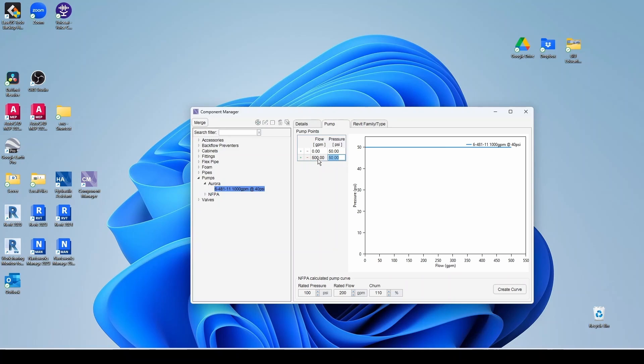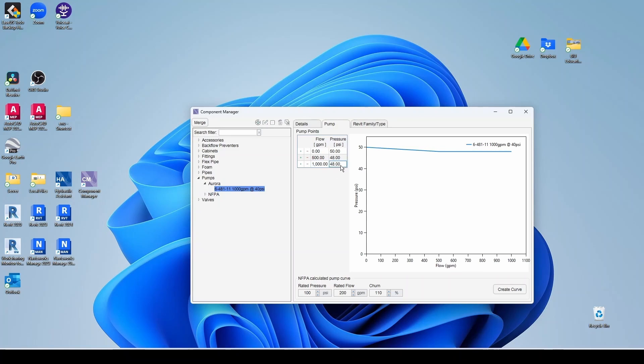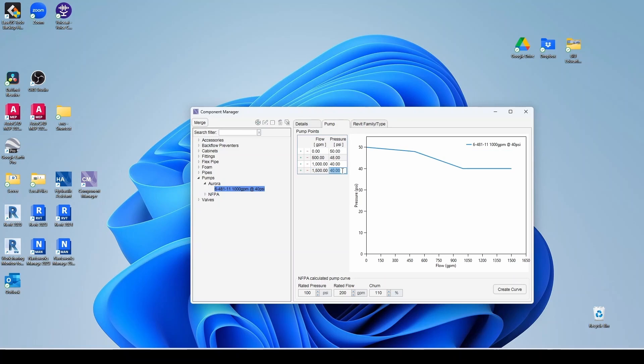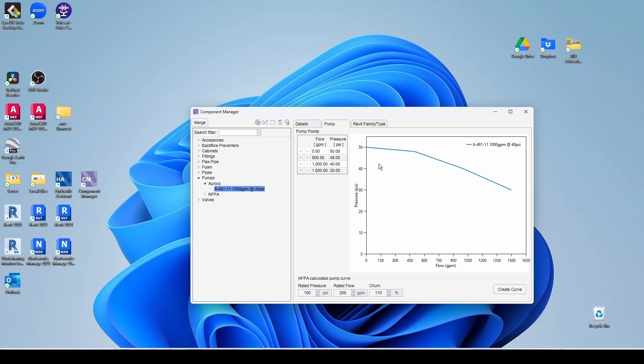Now the rated flow for sure. So at 1,000, we have 40. And then 150% of our flow, we have 30 PSI. And then you can get as granular as you want. You can add a point every 100 GPM if you wanted to. But for most cases, two or three points will be more than enough. So we're done with our pumps. We can close this.